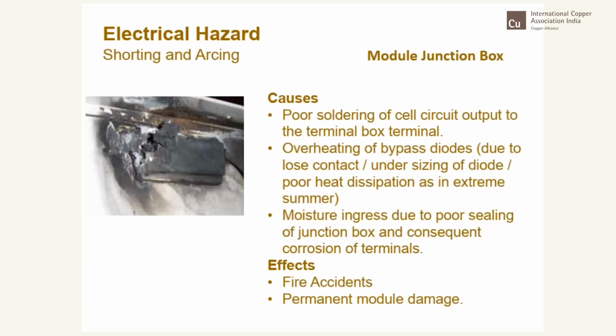Here again, you have a module junction box. Again, it could be because of poor soldering of the cell output circuit to the terminal box terminal. All the modules carry bypass diodes to take care of any shadowing effect, and because of their failure, again, there could be some accidents. Moisture can also interfere and deteriorate the contacts inside, which could also cause problems. Again, the effect is fire accidents and sometimes permanent damage to the module.